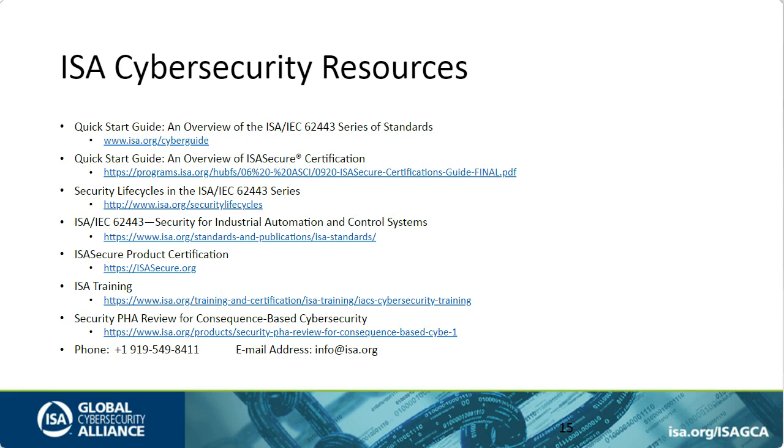So that's by design, actually. The 61511 standard and the life cycle in there was used as one of the source documents to develop Part 4-1, which is the life cycle. Part 4-1 and 3-2 are used as the life cycles. And there is also a working group in ISA 84 that is working on a document that integrates the life cycles that are presented in 61511 and in 62443. So there will be a technical report that comes out pretty soon covering that topic.